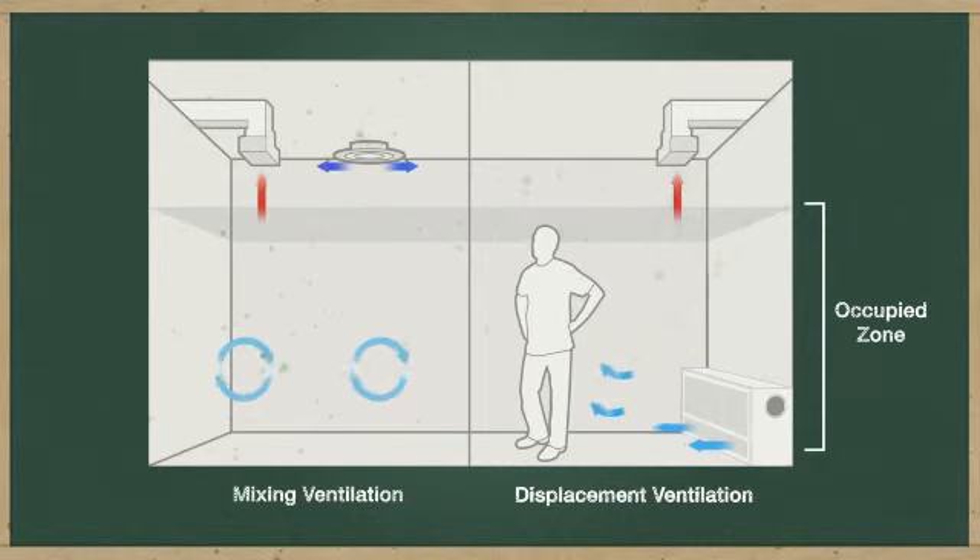Displacement ventilation systems deliver low temperature, low velocity air directly into the occupied zone, relying on the natural buoyancy of the air to drive motion. This results in upward air stratification, which draws contaminants out of the breathing zone and improves overall air quality.